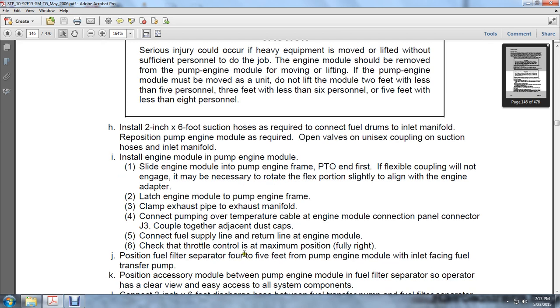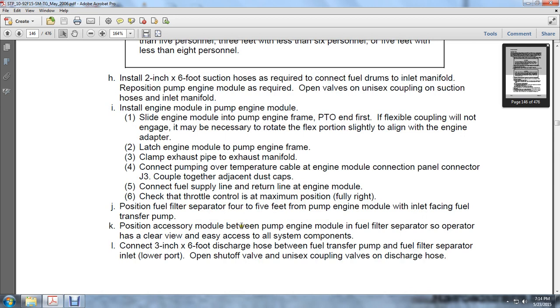Position the fuel filter separator 4 to 5 feet from the pump and engine module, with the inlet facing the fuel transfer pump. Position the accessory module between the pump engine module and the fuel separator so operators have a clear view and easy access to all system components.